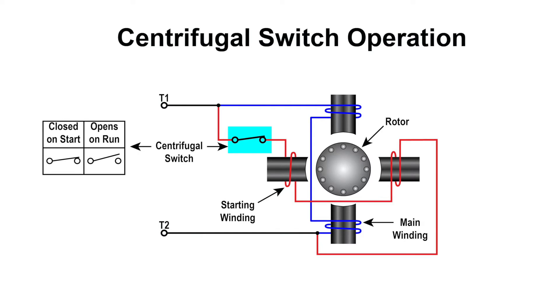In the example provided, when the motor approaches its normal operating speed, the centrifugal force overcomes the spring force, allowing the contacts to open and disconnect the starting winding from the power source. The motor will then continue running through the run windings.